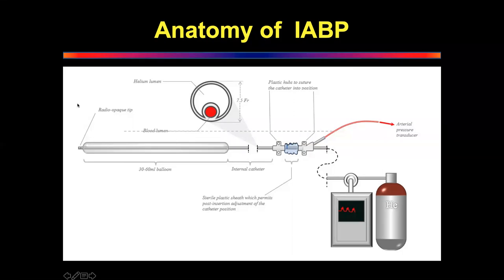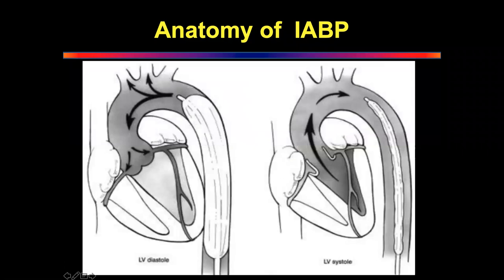There is a fixation device to hold the balloon pump in place. Inside is the lumen of the catheter, and on the outside is the 30 to 60 ml balloon. The tip of the balloon pump always has a radiopaque tip so you can visualize it on X-ray to confirm position. The tip must lie just distal to the left subclavian artery, because the pump is inserted retrograde from the femoral artery.